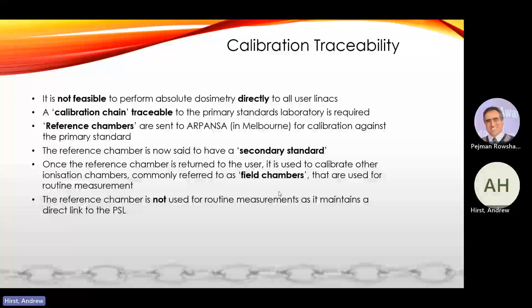So it'd be a good idea to remember those terminologies: reference chamber, field chamber, primary, secondary standard, tertiary, that kind of thing. Yep, so I've just put up the flow, primary standard to secondary to field. And then maybe if it's a secondary standard lab that you have your ion chamber calibrated at, the primary would have transferred down to the secondary and so on. It's just a chain all the way back to the primary lab. But at our hospital, we send ours straight to ARPANSA, and they have the primary standards. This is the process.